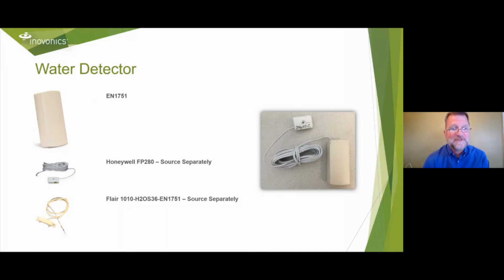This is not an EN1210 — this is our new water detector, the EN1751. It works with both the Honeywell and the Flair probe. I've seen this used at a 50-story high-rise that had the rooftop unit leak and send water down 40 floors through IT closets before they found it. They had a really bad day. We've also used it in 20-story buildings where they've put leak detectors in the lavatories and in the kitchens. It's not always about protecting the walls — sometimes it's about the neighbor's artwork on the walls, on the floor below you. We're starting to see this being driven by insurance companies wanting to make sure that this is all protected.